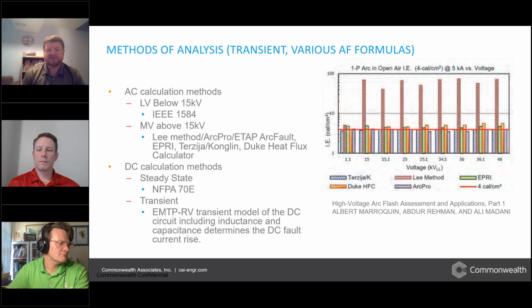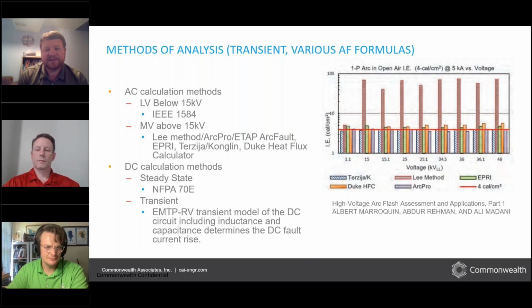So these are kind of the industry standard methods for calculating medium voltage arc flash. When we looked earlier at our example, we talked about some medium voltage conservative results. That's because the IEEE method is given by this Lee method result. The Lee method, as you can see by the graphic, can be sometimes double or even triple of what the other accepted medium voltage arc flash calculation methods are using empirical data. So a lot of times in the industry, we may use one of these other methods, these industry accepted methods for calculating medium voltage arc flash specifically.